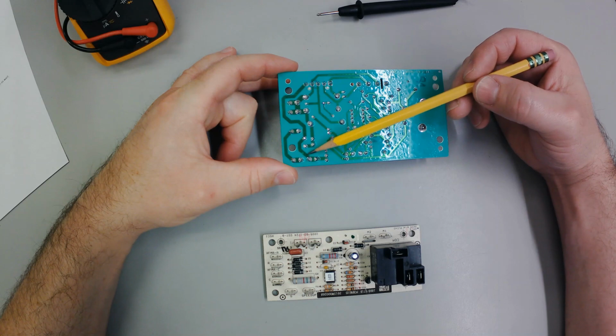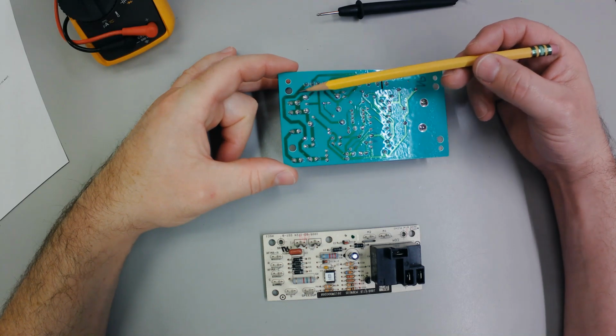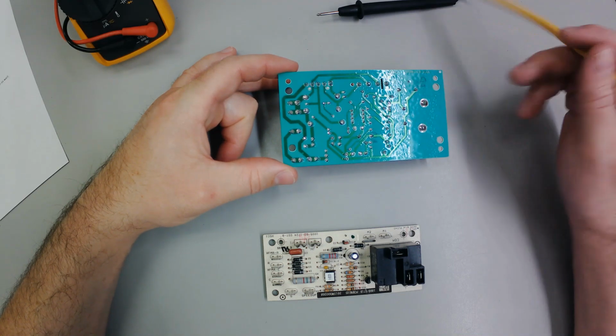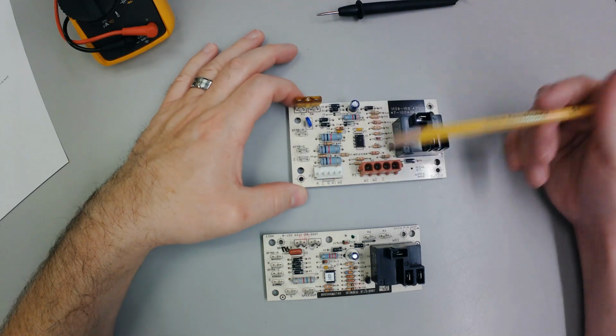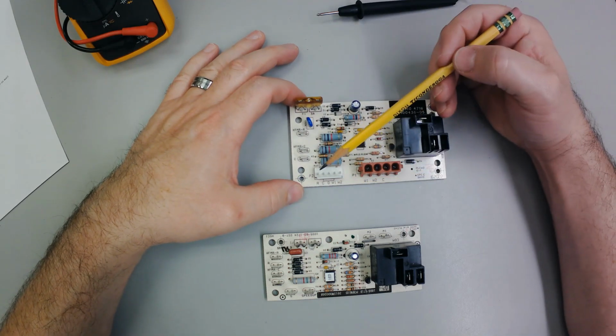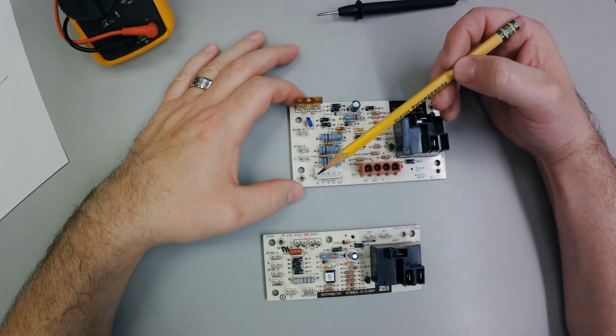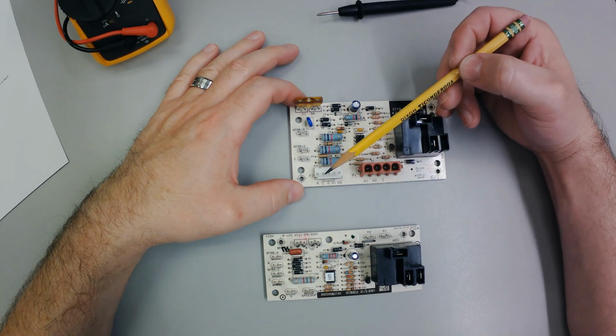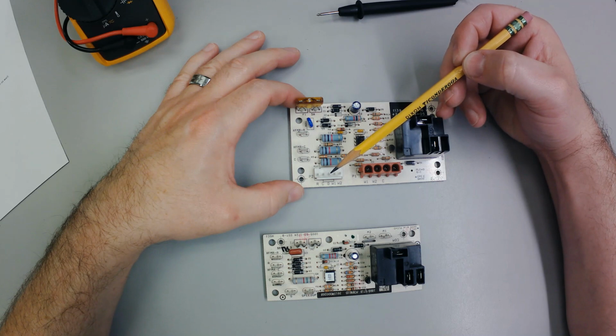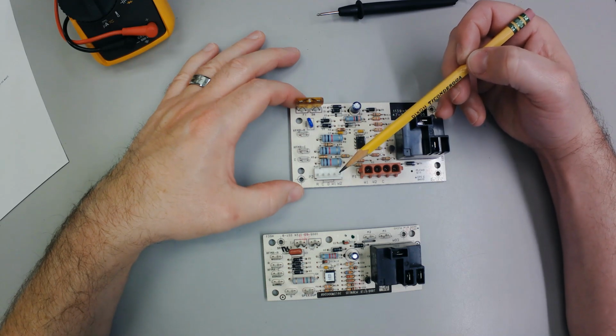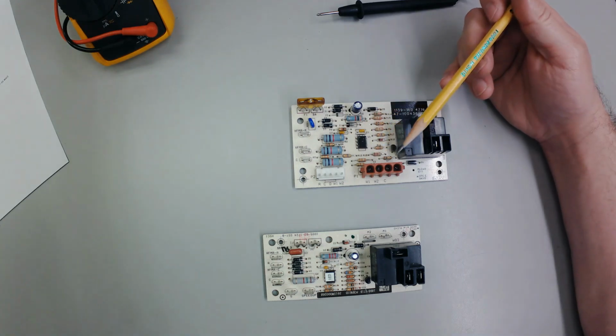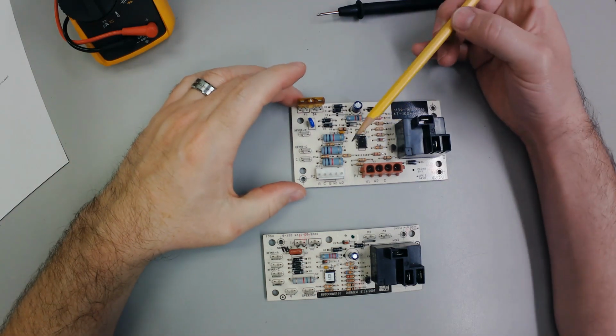So that 24 volts, you can see it just goes down here, and it goes into that first of 5 pins, right? Well, that first of 5 pins is the R. This white plug, this is R going out to your thermostat. This is common coming back from your thermostat. We have a G coming from the thermostat, and your W1, W2 for your sequencer heat relay, whichever you have or whatever you want to call it.